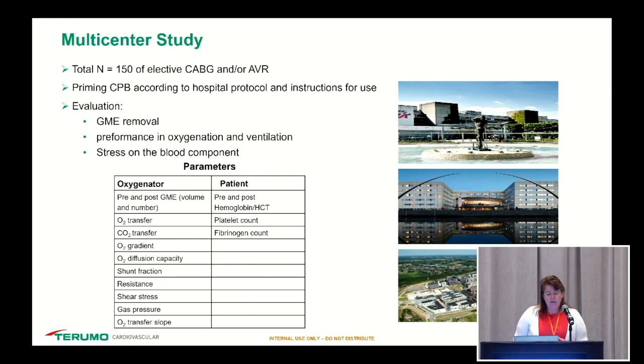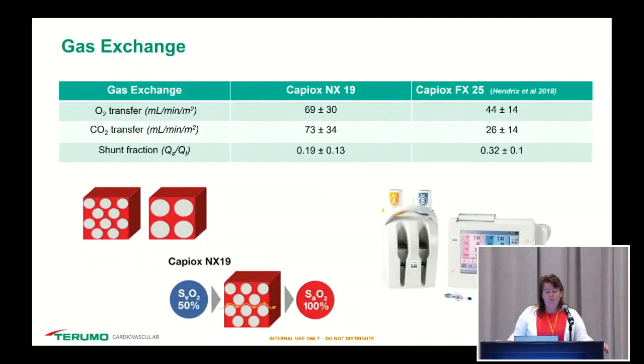These are the parameters that they were looking at. This is the gas exchange, and they used the CDI 550 to measure it. What they were able to show is that the shunt fraction decreased significantly from the FX25. That means the blood coming into the oxygenator is highly likely to have gas exchange before it is removed from the oxygenator. As you can see, it went from 0.32 to 0.19. That is a significant decrease, meaning that gas exchange will happen within that oxygenator. And as you can see, they increased the O2 transfer and the CO2 transfer as well.